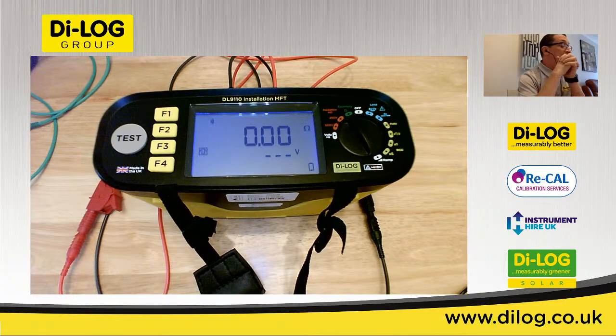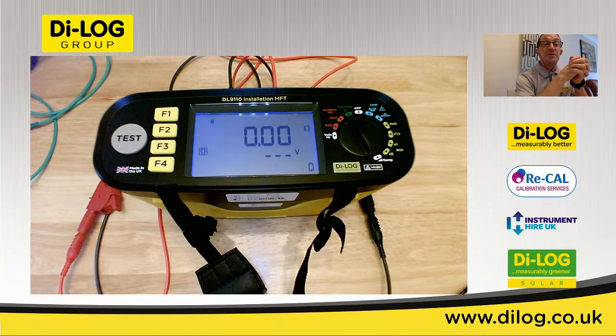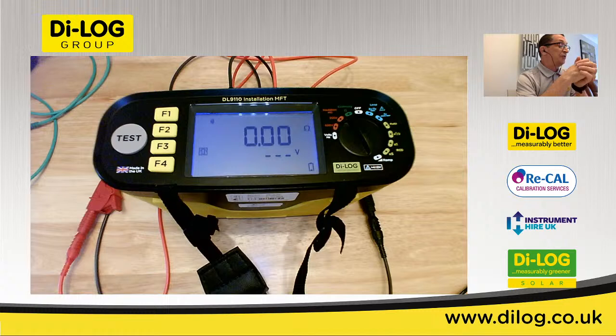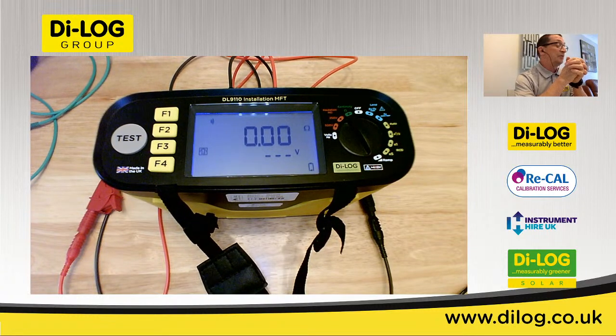Incidentally, the nulling of the test leads will stay there until you either replace the batteries or you replace your test leads. If the leads become damaged and you just want to replace your test leads, then it's good practice to zero the test leads just to make sure.